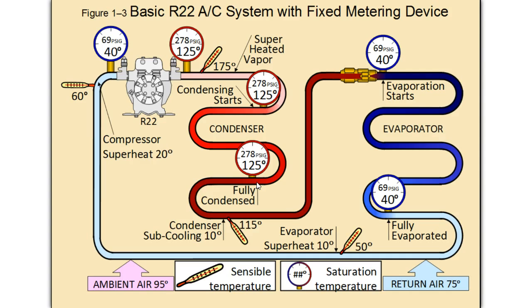At this point it is 100% liquid and cannot change state anymore, and it becomes sub-cooled, so that we have a solid column of liquid entering the metering device. It enters the metering device, which drops the pressure of the refrigerant.